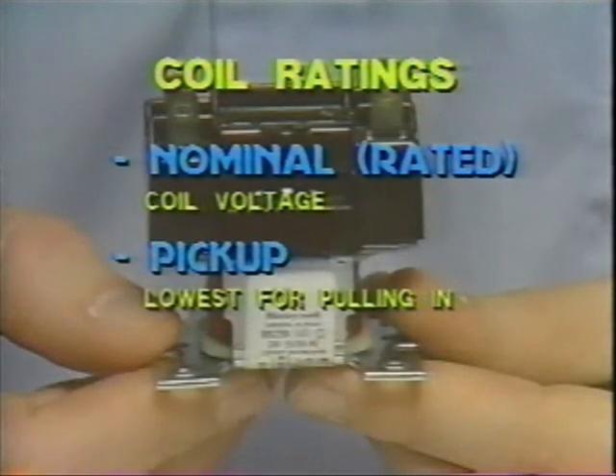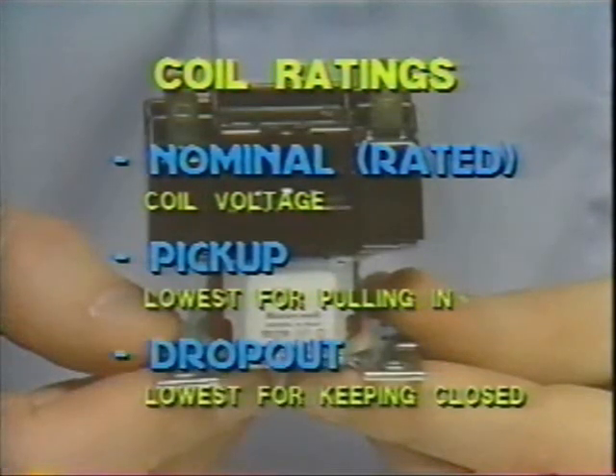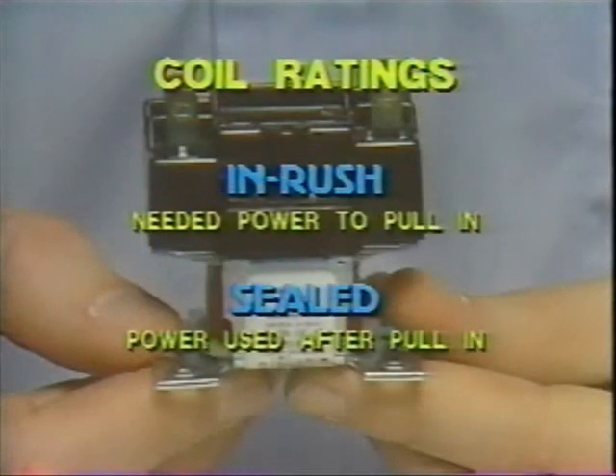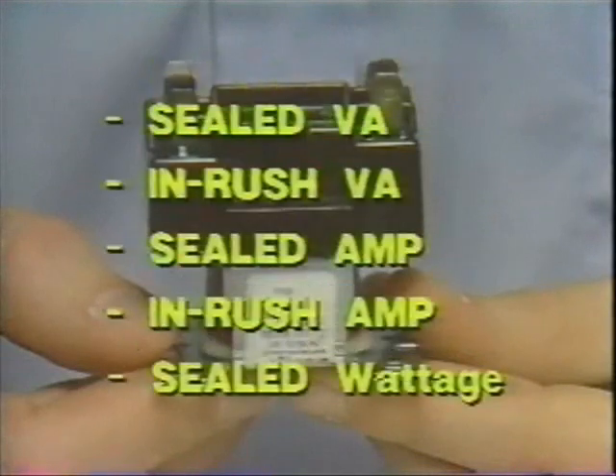Pickup voltage is the lowest average voltage needed to pull in a relay. Dropout voltage is the minimum needed to keep the contacts closed once a relay pulls in. The terms inrush and sealed relate to how much power and/or current is used to pull in a relay versus how much is used on a continuing basis after it has pulled in.